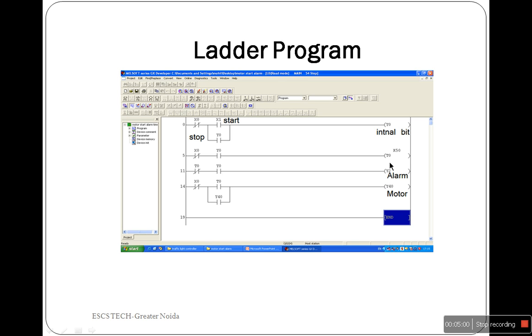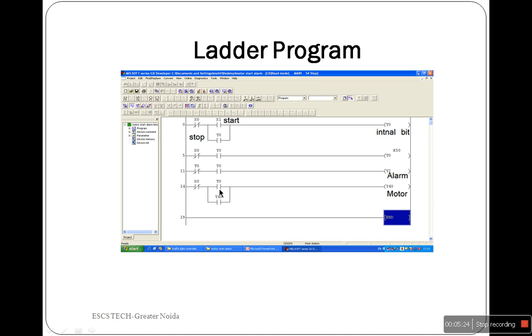Time delay relay T0 gives the 5 seconds delay for output Y1 which is associated with the alarm and waits to turn off until delay is completed. Normally open contact T0 waits to close until delay is completed, then the motor will start and continue running until X0 is pressed. X0 is the stop switch.